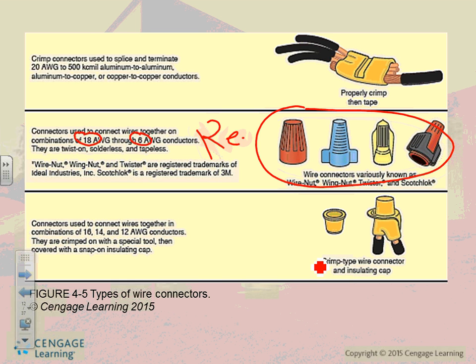And commercial too, up to this would get you up to circuits probably. Number 6 will get you up to a 50 amp circuit, guys. So look at this right here above your head: 20 amp circuits, 30 amp circuits, 40 amp circuits, and 50 amp circuits. You can get away with wire nuts, no problem. What happens if you go to a 100 amp wire?